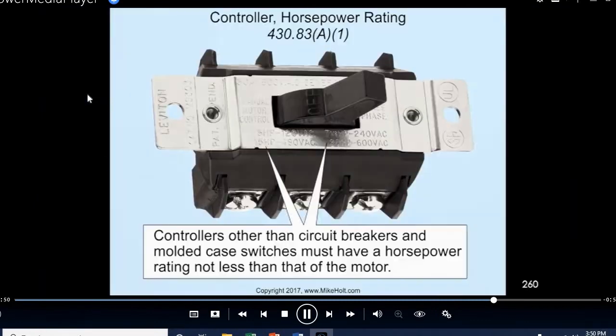Motor controllers. Controller rating. When you're using a controller which is making and breaking contacts, controllers other than circuit breakers and molded case switches must have a horsepower rating not less than that of the motor. So when you have a controller other than a circuit breaker or a molded case switch, it has to have a horsepower rating. Now, horsepower rating means the switch is designed to take 6 times the locked rotor current rating. That's what a horsepower rated switch is for.